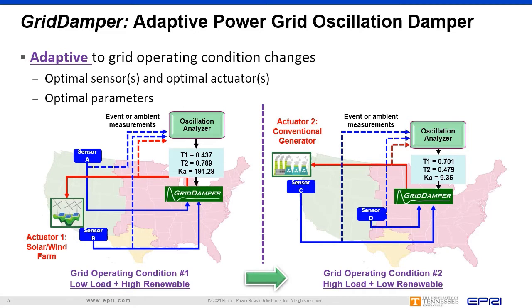Power grid operating conditions change due to variations in load demand and power generation. These variations are common in daily grid operation and become more frequent because of the intermittent nature of renewable energy sources. Grid Damper automatically monitors oscillations with real-time measurements and updates its choice of sensors and actuator equipment for optimal observability and controllability. The figure shows an example in the Western Interconnection where Grid Damper automatically changed sensors from AB to CD as the operating condition changed.